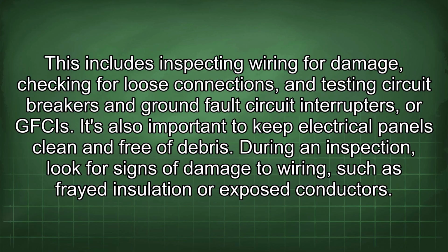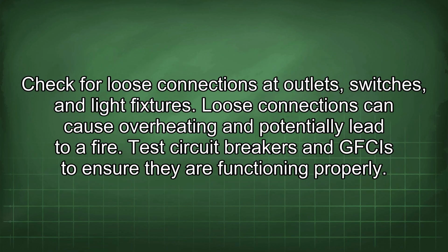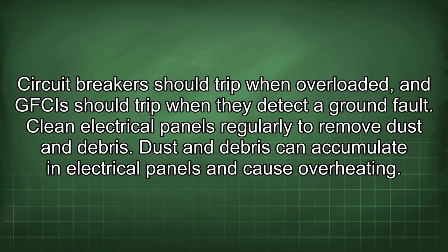GFCIs. It's also important to keep electrical panels clean and free of debris. During an inspection, look for signs of damage to wiring, such as frayed insulation or exposed conductors. Check for loose connections at outlets, switches, and light fixtures. Loose connections can cause overheating and potentially lead to a fire. Test circuit breakers and GFCIs to ensure they are functioning properly. Circuit breakers should trip when overloaded, and GFCIs should trip when they detect a ground fault.